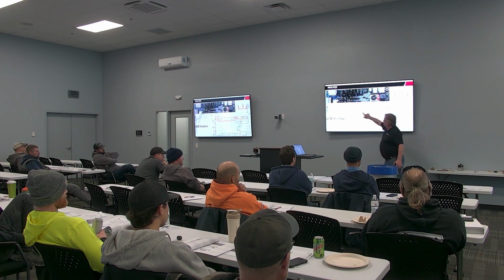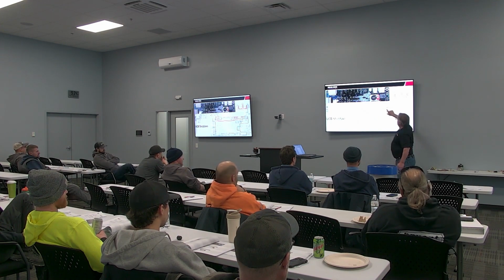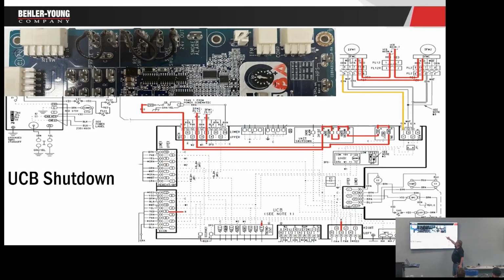Because if I follow it, it goes right to the transformer. So your smoke detector is going to break this. So I'm going to unplug this jumper. And the reason I'm bringing this up now is because this, Kelly, goes back to what I said about changing things. I had a contractor call last week. We have a problem with our smoke detectors, because when he's doing a smoke test, he keeps losing his 24 volts. So what was happening is he was using these terminals here, the RC, and when he tests a smoke detector, it would kill all 24 volts and reset everything. So he thought there was a problem with the smoke detector.